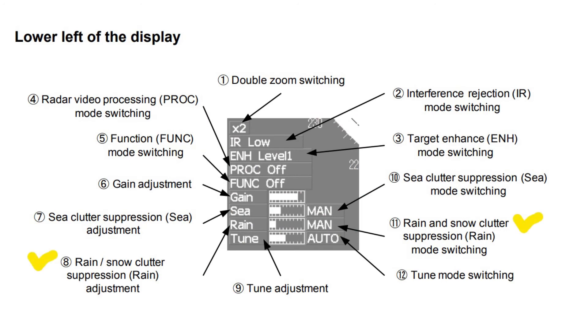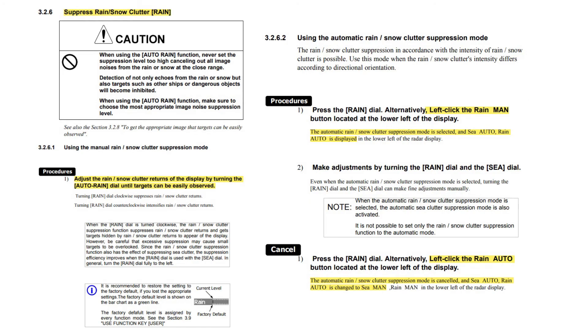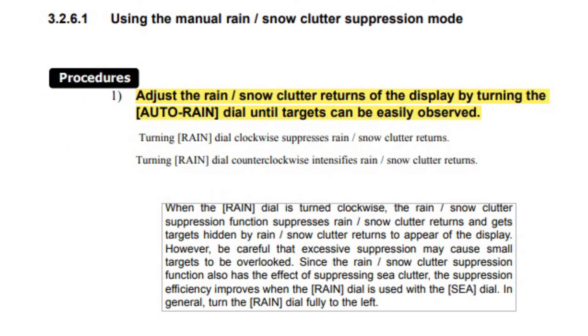Rain/snow clutter suppression adjustment: when the RAIN dial is turned clockwise, the rain/snow clutter suppression function suppresses rain/snow clutter returns and gets targets hidden by rain/snow clutter to appear on the display. Be careful that excessive suppression may cause small targets to be overlooked. Since the rain/snow clutter suppression function also has the effect of suppressing sea clutter, suppression efficiency improves when the RAIN dial is used together with the SEA dial. In general, turn the RAIN dial fully to the left.